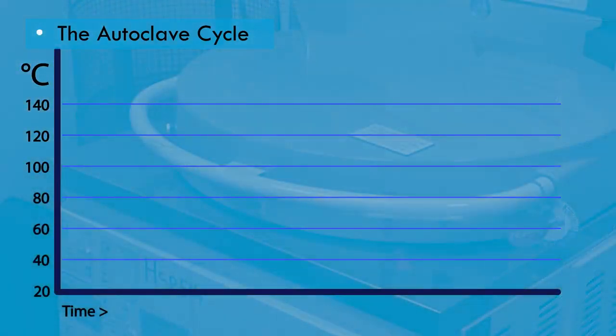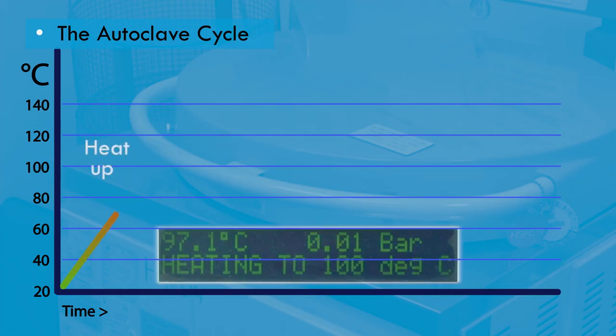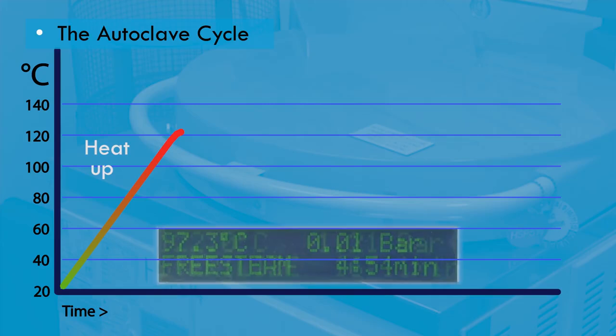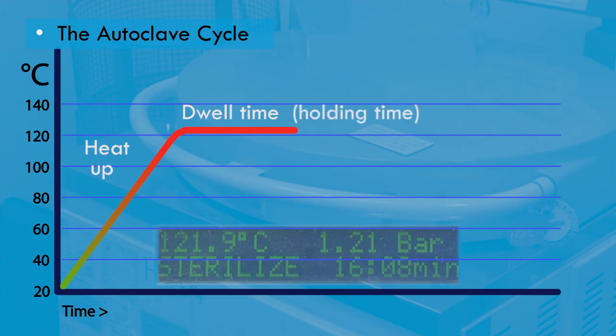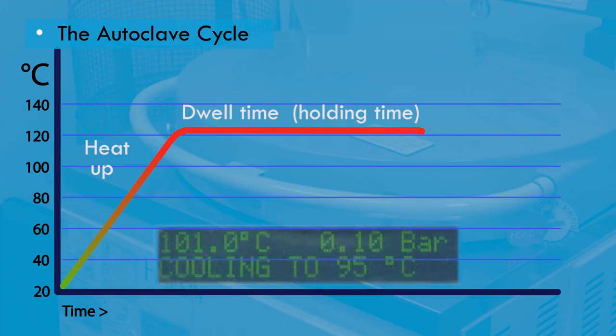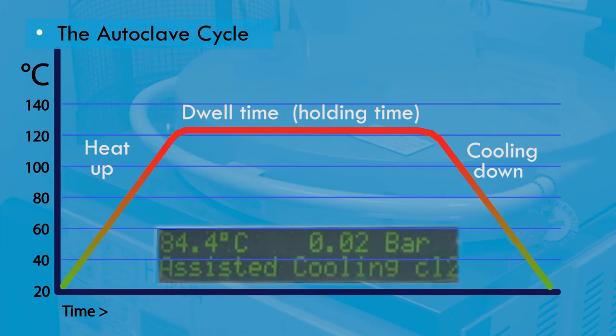The autoclave cycle consists of 3 phases. In the heat-up phase, temperature and pressure are raised to preset values. Some autoclaves create a partial vacuum during this phase to help steam penetrate the load. During the dwell time or holding time, the autoclave maintains a constant temperature and pressure to ensure sterilization. During the cooling down phase, heat and pressure are allowed to fall to ambient levels. In some autoclaves, there may be an assisted cooling function to reduce the overall cycle time.